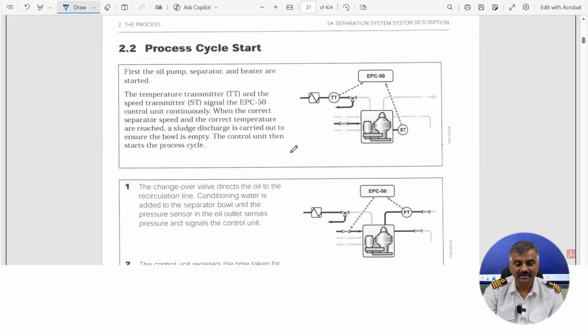Now we will understand how the process actually starts in the purifier. When we put on the purifier, the oil pump, separator and heater are started. We can see here the heater, oil pump and the purifier is started. Once the purifier achieves the rated RPM, then there is a temperature transmitter. We have seen in the previous video TT1 and TT2 temperature transmitters in the inlet line, and there is this speed transmitter ST, which signals the EPC 50 control unit. For the oil feed temperature to come in, you need a temperature transmitter, otherwise the oil will be recirculated until the temperature has come.